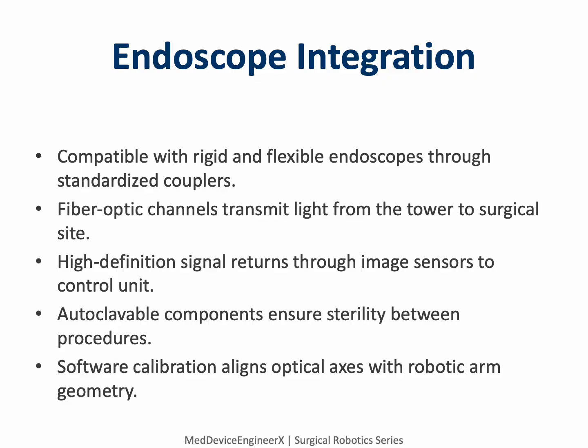Endoscope integration completes Hugo's visual pathway from patient to console. The system supports both rigid and flexible endoscopes, depending on the surgical specialty. Light travels from the tower's illumination module through fiber optic bundles, entering the surgical field as bright, even illumination. The returning image passes through lenses and filters before reaching the 3D HD camera sensors. Each connection, mechanical, optical, and digital, is standardized, enabling quick setup and secure locking during docking.